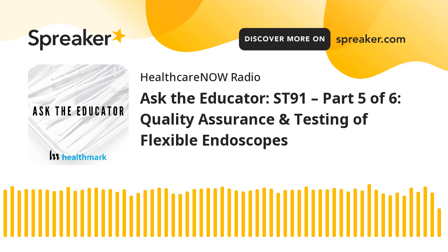And what we're seeing now as new scopes are brought out on the market, or older scopes, their IFUs are updated. We see new requirements in the IFUs for doing these inspection steps, where to focus, what to look for, at what stage in the process, not only after manual cleaning, where we're kind of used to doing it anyway, but really emphasizing in the procedure room before reuse on the patient, again, because the scope could be damaged during disinfection, it could be damaged during sterilization, and you wouldn't catch that, and then that would be used on the patient. So also emphasizing inspection in the procedure room right before the procedure itself.